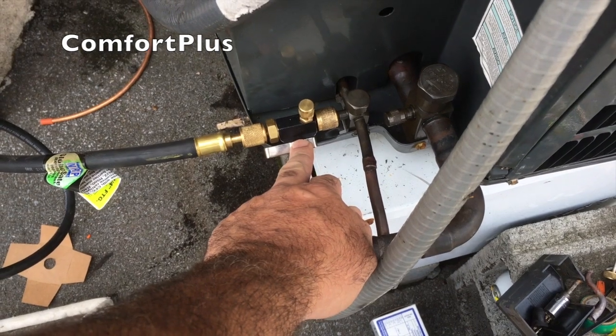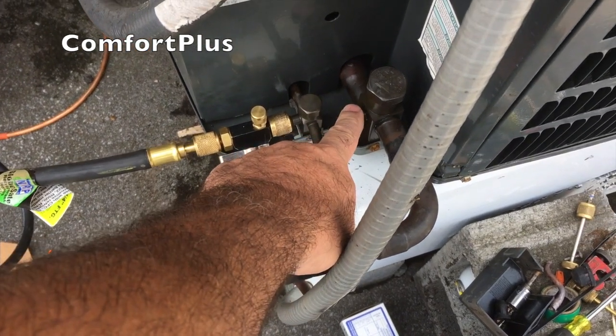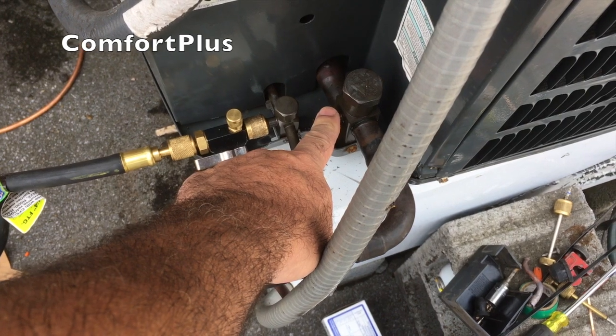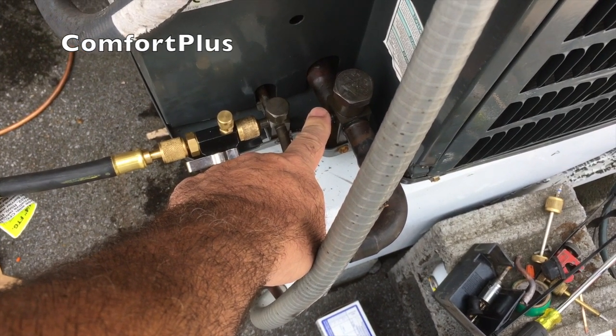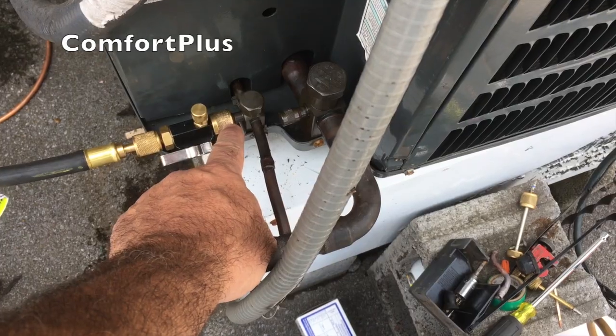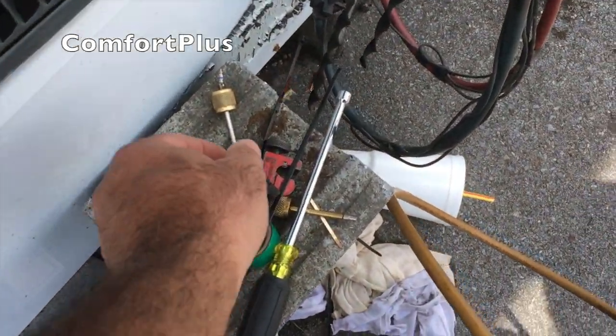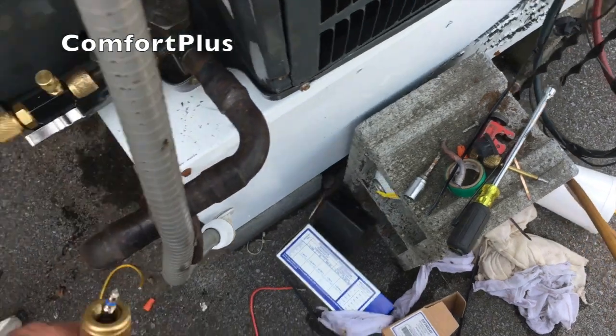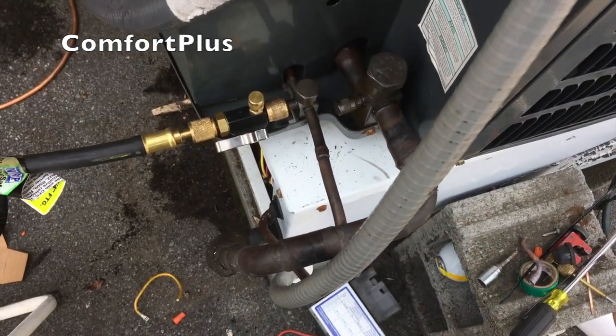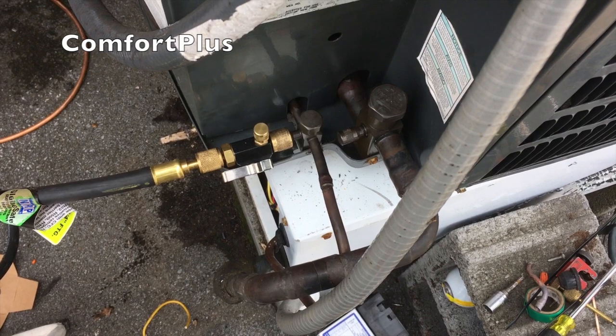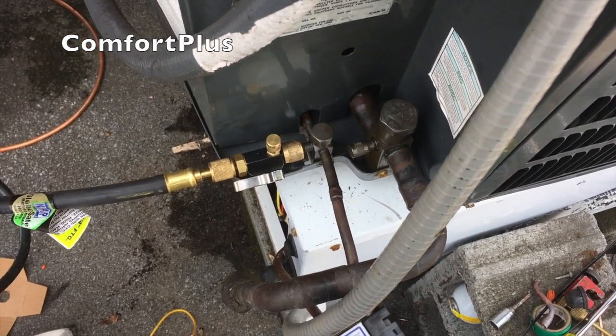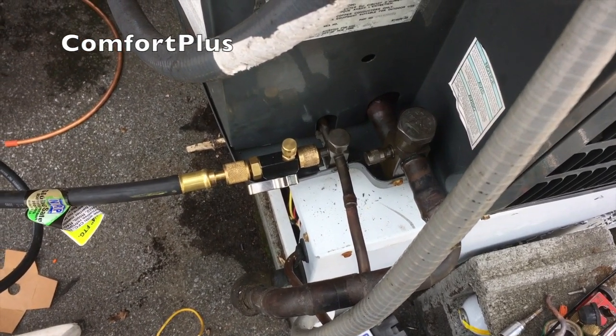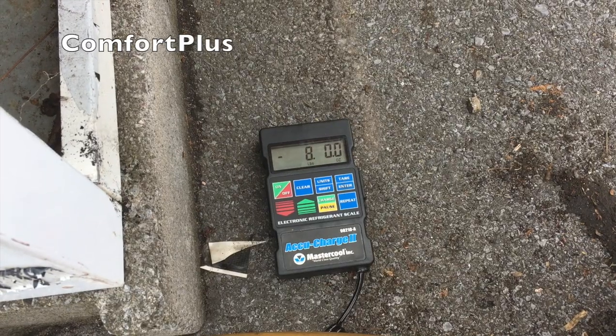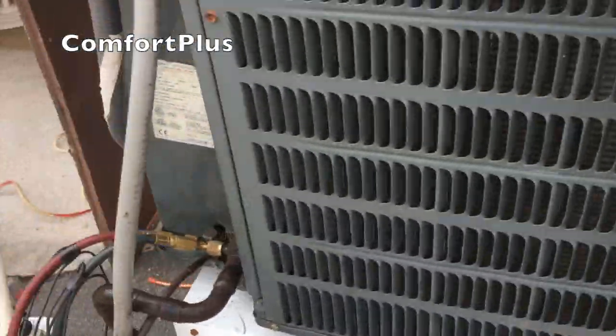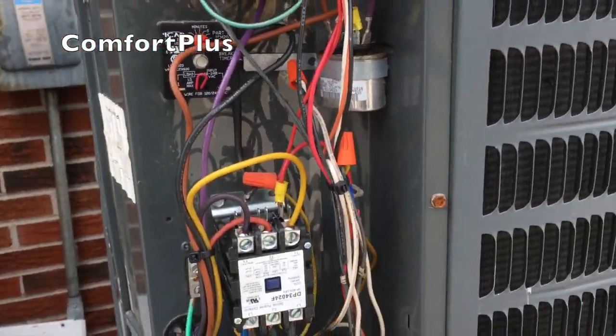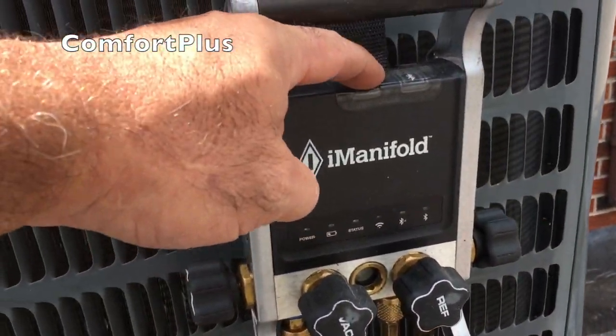turn off my vacuum pump and start putting the 407C in on the low side in order to break the vacuum. Then I will put my valve core back in and add about 7.5 pounds, 7.5 to 8 pounds of 407C and start it up and see where we are. Okay, I'm going to stop right there at 8 pounds and flip it on and check the pressures.